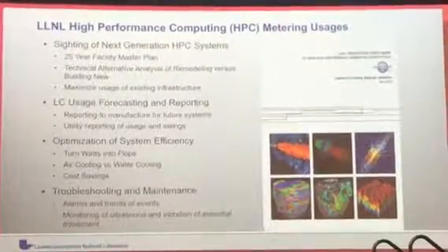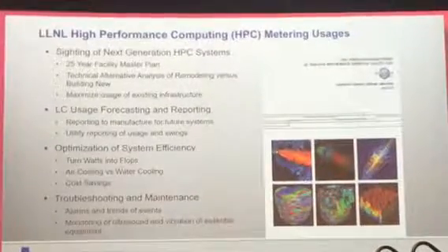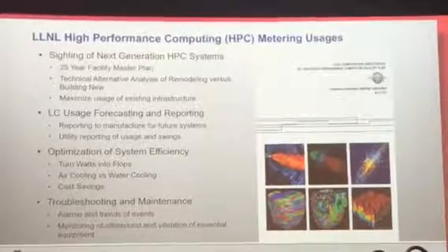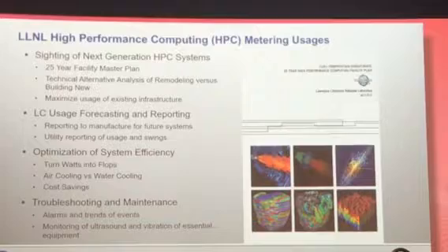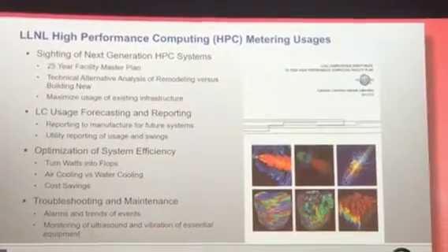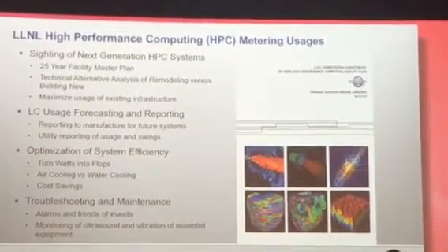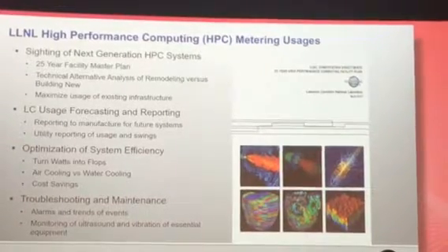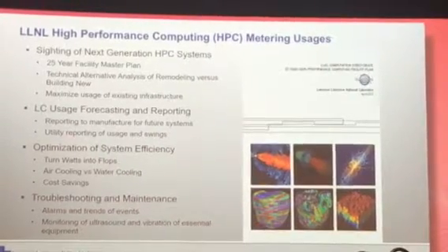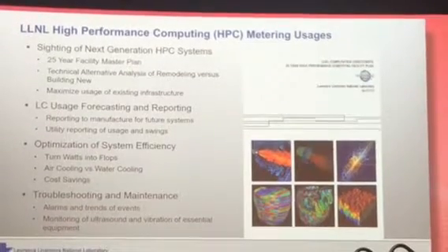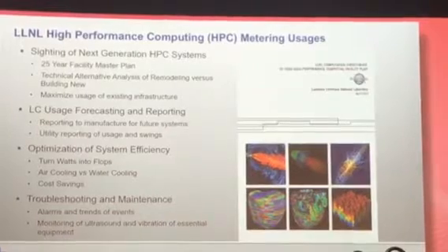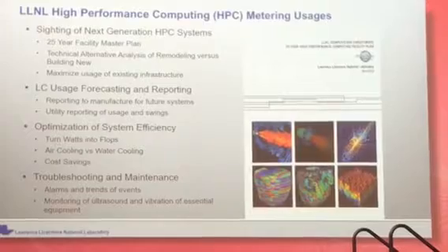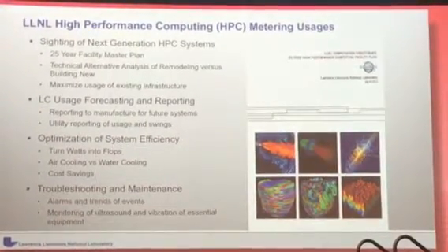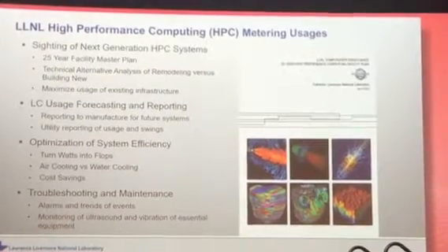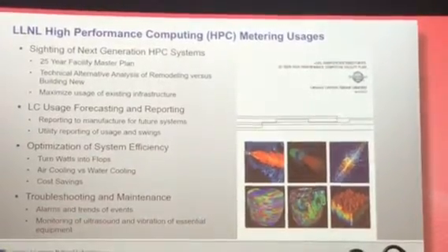So once we get that data, our biggest concern is to site next generation HPC systems called ATS machines, advanced technology systems. We always have to know what we're using and be able to show what kind of capacity we have at our facilities. With these huge block loads, forecasting and talking to our utility company is important, so we can notify them of any power swings. And then we have to work with our users to optimize the system's efficiency. Our biggest goal is to turn as many of our megawatts into flops, floating point operations per second. And also look into possibly moving more into water-cooled solutions and cost savings. And then most recently, we're looking into troubleshooting and maintenance of our essential mechanical equipment, basically seeing if we could get away from time-based maintenance and go towards as-needed maintenance.